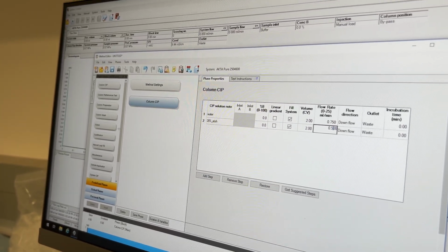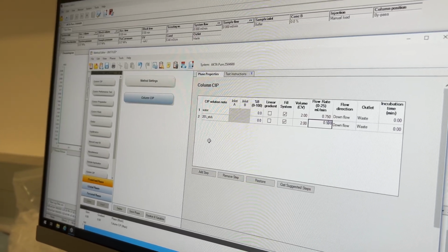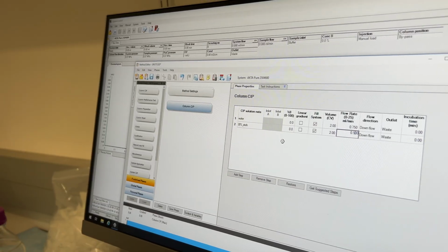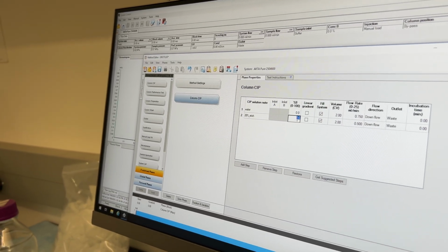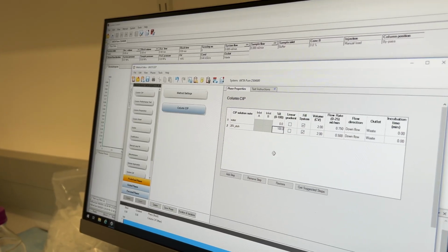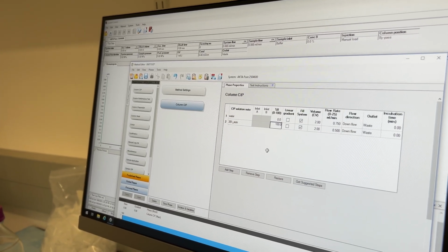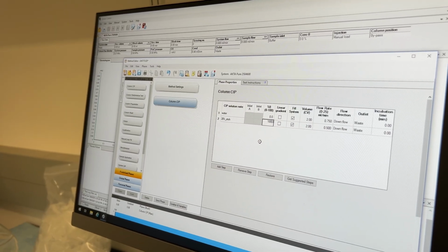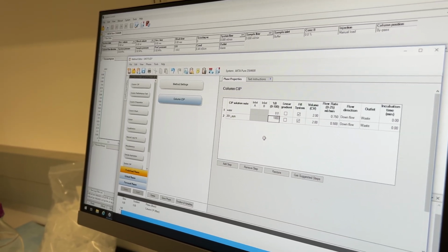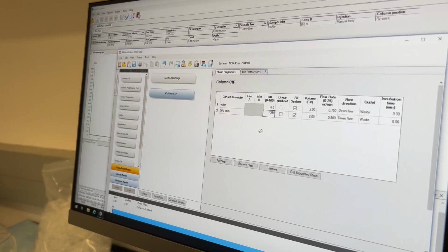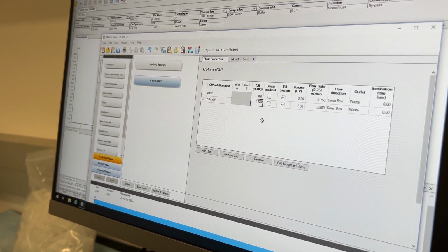Oh, sorry. One thing we need to do though, because the ethanol, what line is the ethanol in? The B line, right. Yes. So we're going to set that to 100%. Perfect. And since the buffer and the ethanol lines are in different pump lines, we can go ahead and do it without having to stop in between to change our line to wash it with water and then with ethanol, because the one's already in the ethanol.